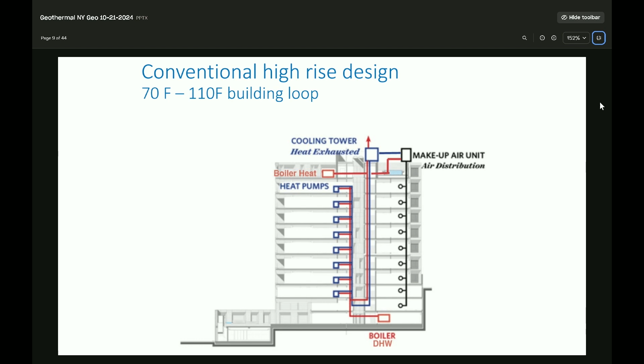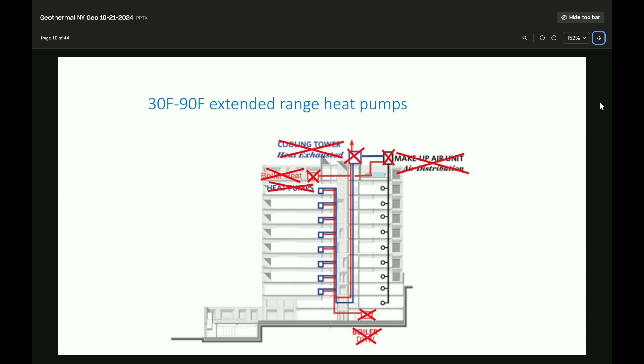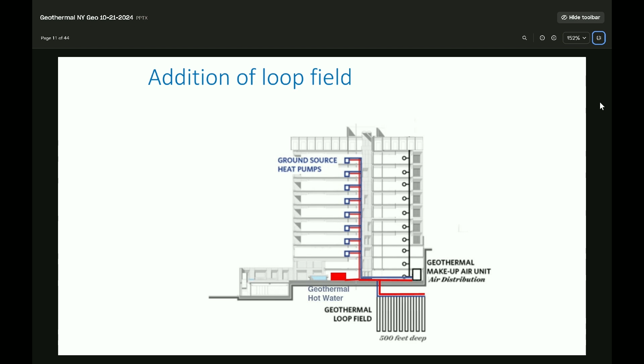Every big building I'm aware of nowadays is designed with heat pumps, and because every tenant wants to control his own destiny, you have a cooling tower on top to get rid of heat, and when the loop is cooling down too much, a boiler injects heat into the loop. But why don't we store that instead? All we need is to get rid of all that infrastructure and just put in a loop field.